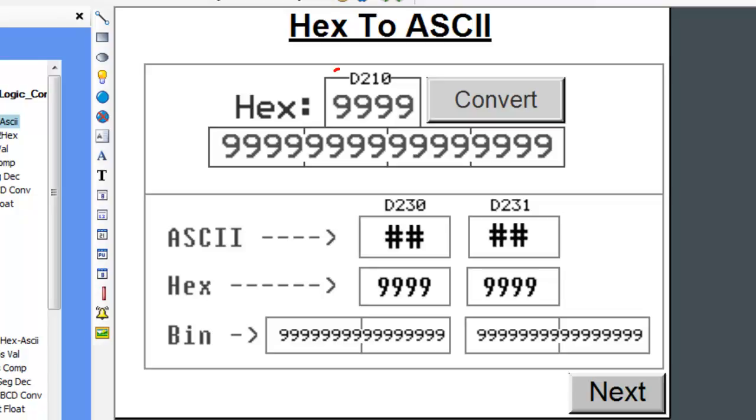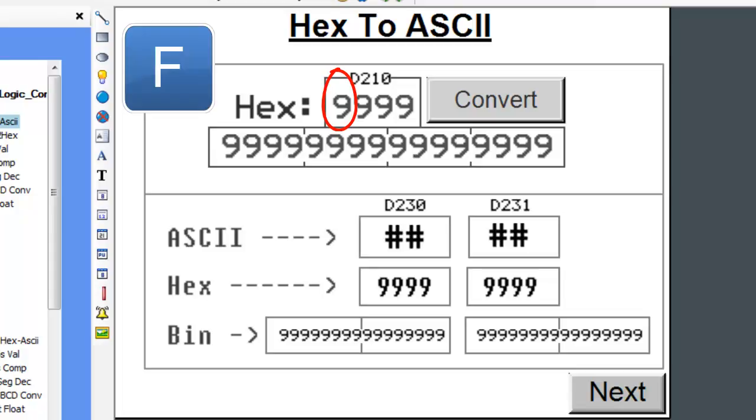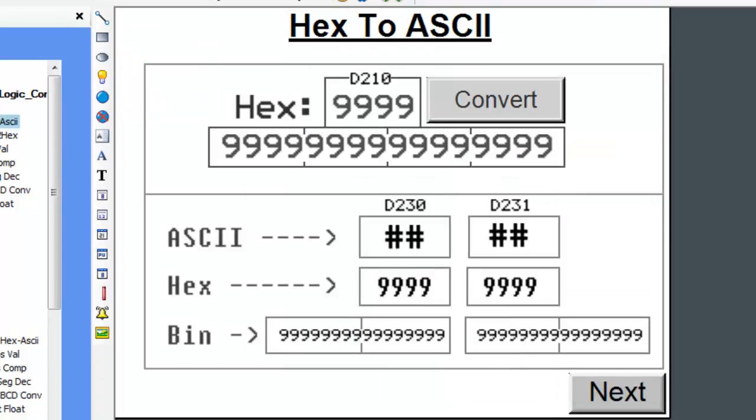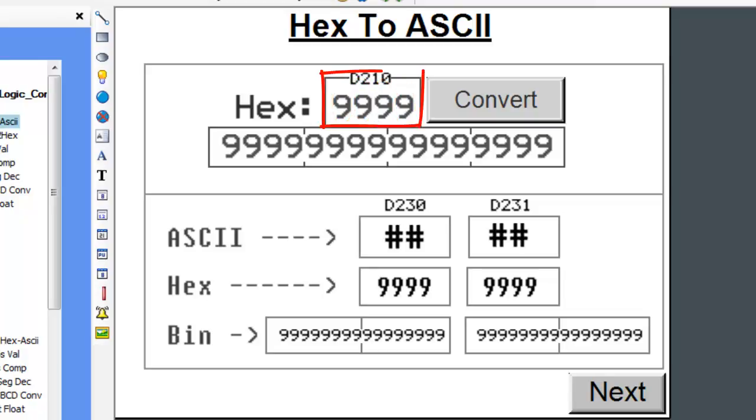A hex value uses less space than an ASCII value. The maximum single value for a hex is the letter F, which represents the number 15. The number 15 in binary is 1111, which is 4 bits. Since each data register has 16 bits in it, we can store a 4 hex value in one register. That is why, for every 1 full hex represented data register, we need 2 ASCII represented data registers.